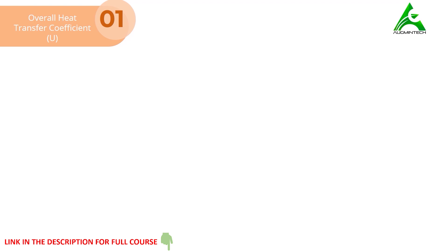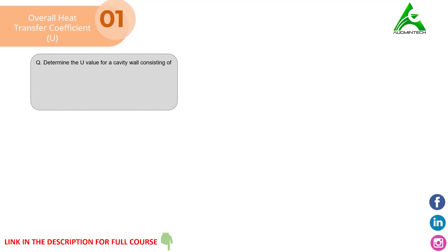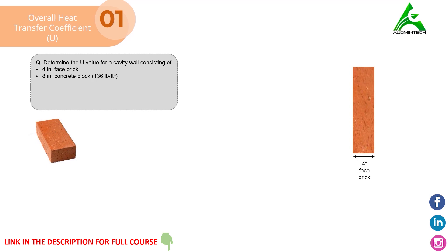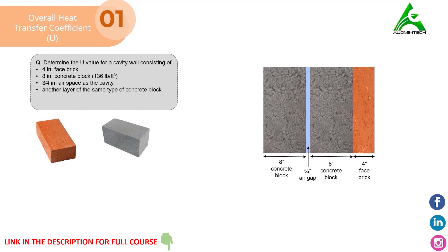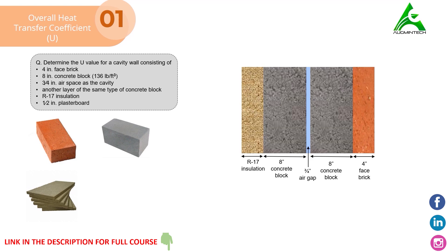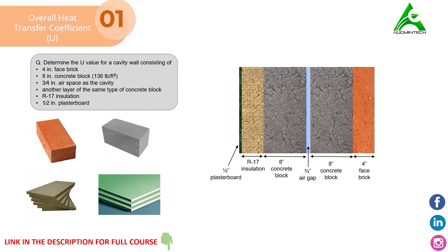We'll do a sample problem to understand how to find the value of U when information about the components used in the construction of a wall is provided. The question says: Determine the value of U for a cavity wall consisting of a 4-inch face brick, 8-inch concrete block, 3/4-inch air space as the cavity, another layer of the same type of concrete block, R-17 insulation, and half-inch plasterboard. Based on this information, we'll find the value of U with the help of charts and tables provided by ASHRAE.